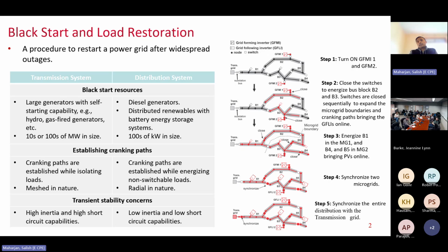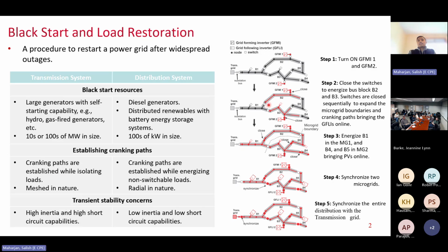So let's look at the typical black start and load restoration process in a very simple distribution network with two grid forming inverters, okay, and many grid following inverters. This diagram on the right-hand side gives you an idea of how the black start is done. For a very simple system, we don't have to optimize. We can simply use our intuition to determine a proper sequence for black starting the whole system.